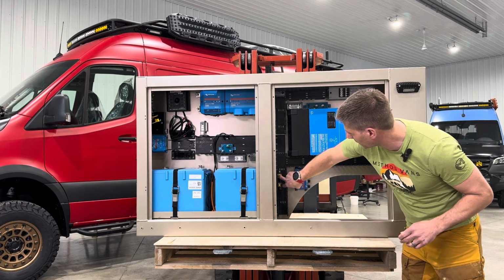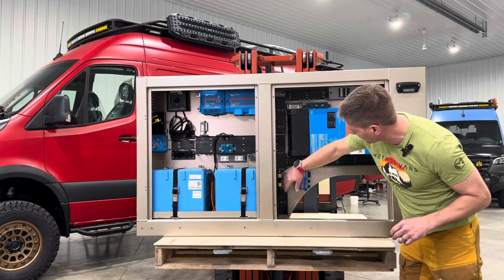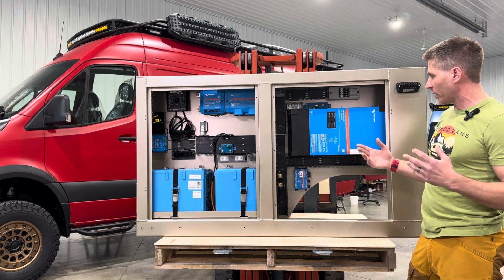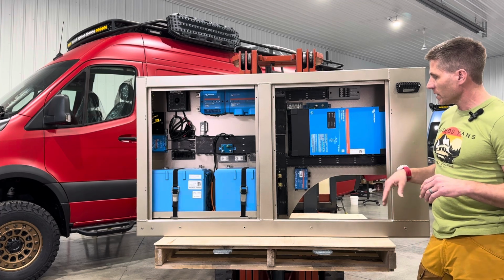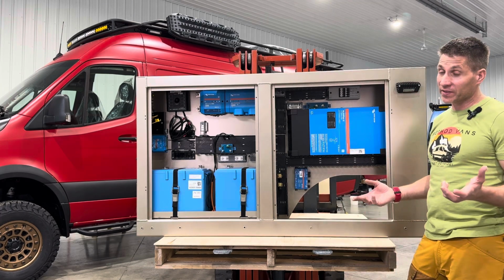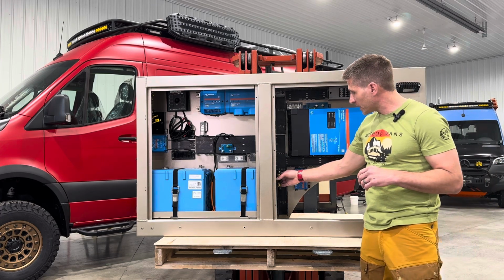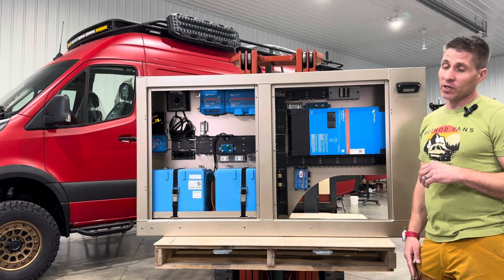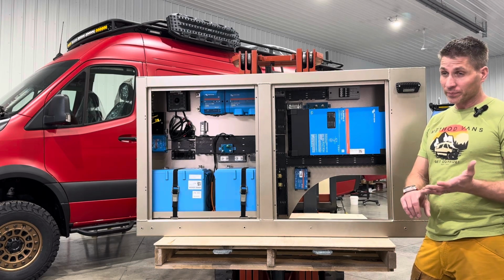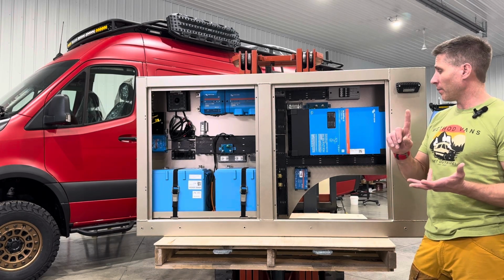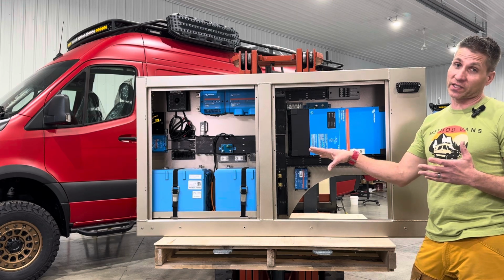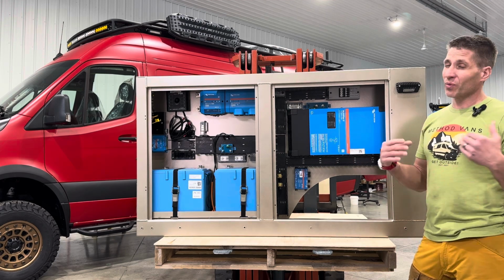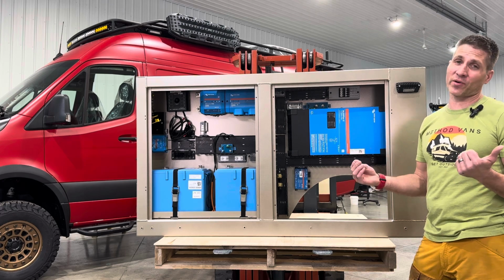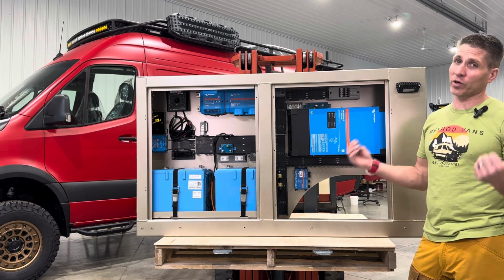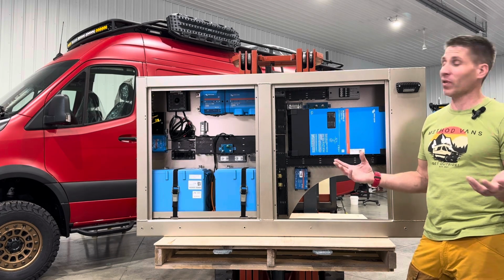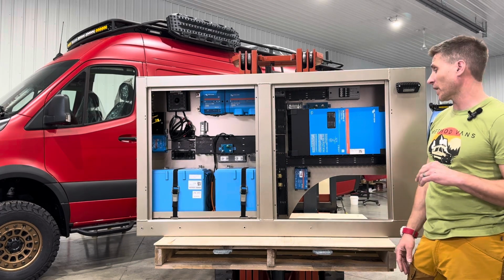Here you'll see a shunt, mounted inside the tracking on purpose—one, so it's hidden, and two, it's a perfect path for us. The shunt is monitored off the negative side of the system, and it's specific to our secondary alternator. All of our builds have a 280 amp secondary alternator that recharges our system at very high rates when the van is running. We'll typically see upwards of 220 to 230 amps hitting our battery system while driving. That's exceptional—you drive a couple hours and can completely recharge your entire bank.